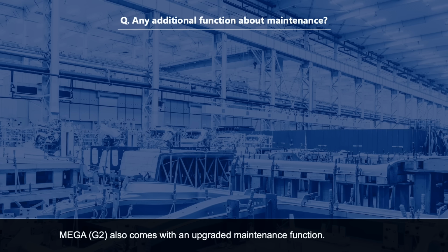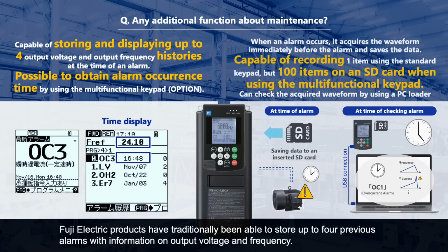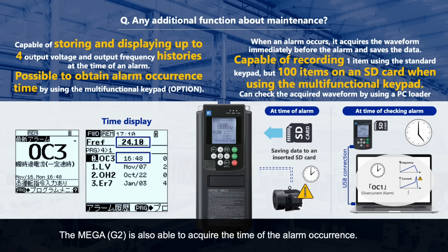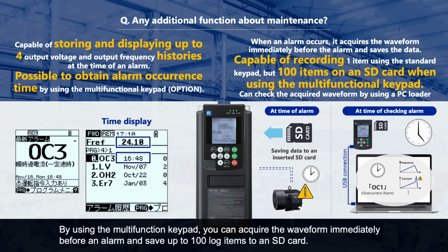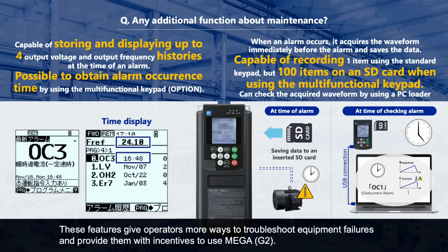MEGA G2 also comes with an upgraded maintenance function. Fuji Electric products have traditionally been able to store up to 4 previous alarms with information on output voltage and frequency. The MEGA G2 is also able to acquire the time of the alarm occurrence. By using the multifunction keypad, you can acquire the waveform immediately before an alarm and save up to 100 log items to an SD card. These features give operators more ways to troubleshoot equipment failures and provide them with incentives to use MEGA G2.